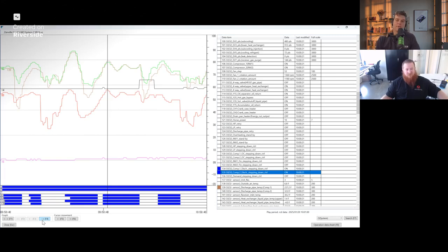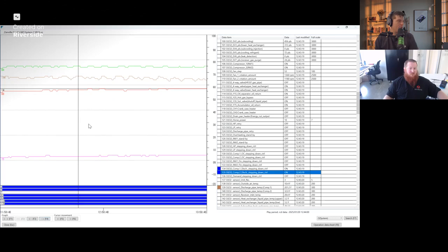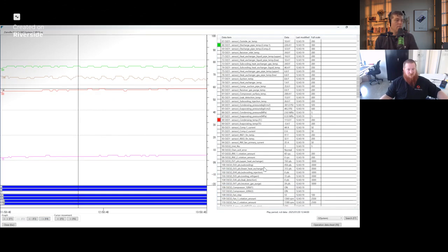It's got to build head pressure, shift four-way valves, do all this fun stuff. But eventually it will level out and it'll show you what the issue is, or what the issue looks like after it's leveled out for a while. So even if we jump in here where lines aren't changing drastically, we're still in safety control mode.